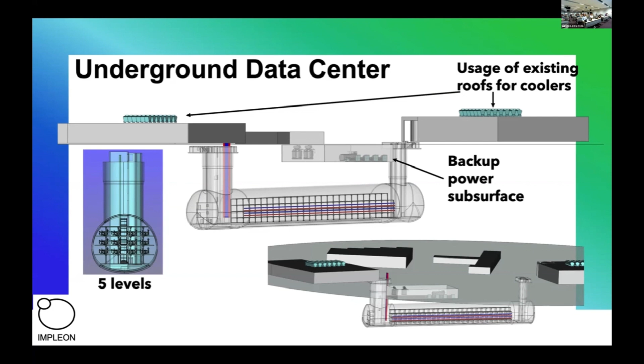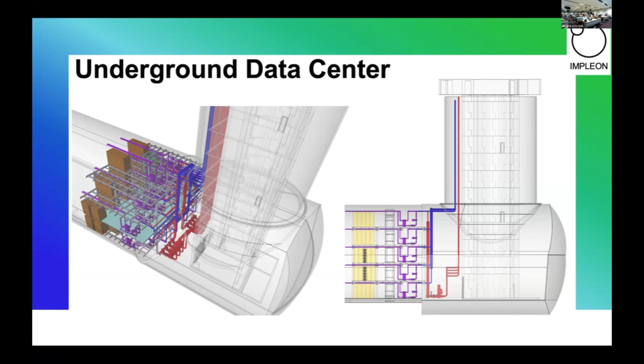This is an open source solution we created, and this is how it looks. We designed it so air-cooled racks with backdoor cooling can be very dense, using every cubic meter of the space. You can see how the pipes and heat exchange subsystem are placed. There are 44 rows, each with 75 racks, all identical.